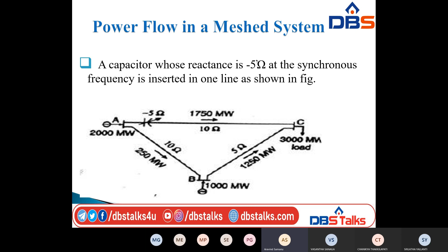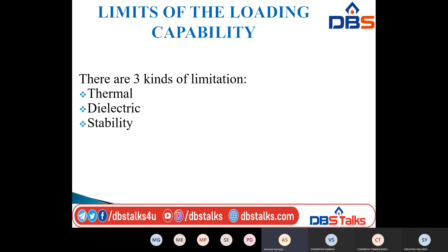So here I told you there are three kinds of limitations for the loading capability: thermal, dielectric, and stability. The first one is thermal. Thermal means the thermal capability of an overhead line. The thermal capability of an overhead line is a function of the ambient temperature, that means different temperatures, and wind conditions, condition of the conductor, and ground clearance. Depending upon these conditions, the overhead line is functioning.